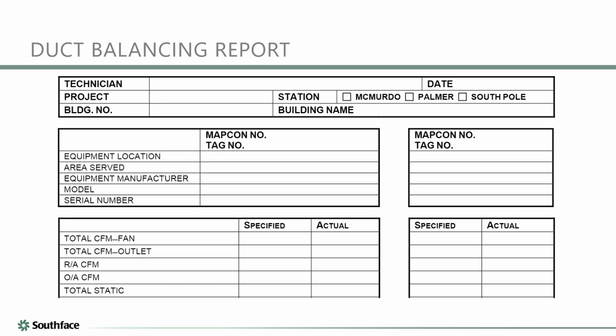Yeah, speaking of the report, here's what one would look like. Again, if you're lucky enough to get one, but if we're going down this pathway, we have to be able to see this in order to meet the code. So there are going to be temperatures in there at some point, your delta T's, but for the most part, we're looking at airflow measured in CFM, usually using something like a flow capture hood.